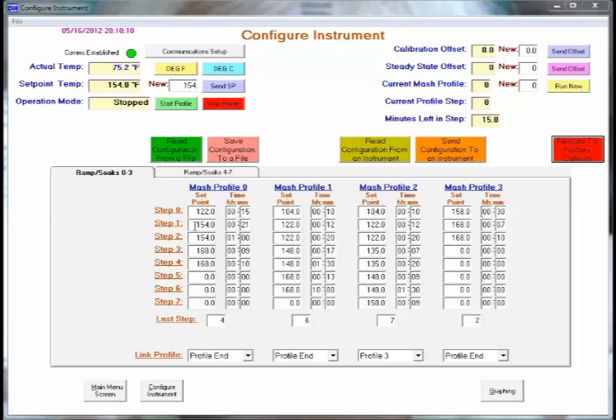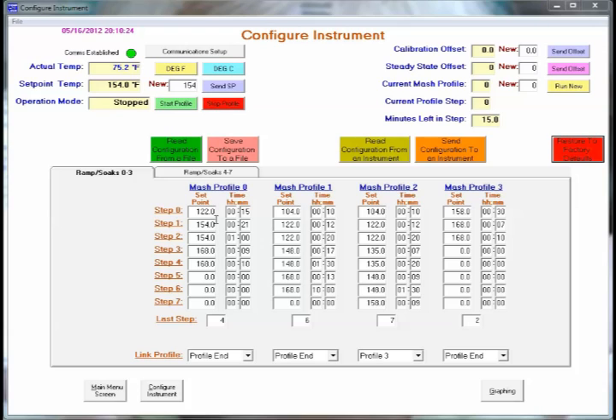After that we're going to ramp and we're going to ramp from up to 154 and we're going to ramp at a rate of one and a half degrees per minute. So to calculate the time we take 154 minus 122 and divide by 1.5. That would be 21 minutes. So it will take us 21 minutes to ramp from 122 to 154 degrees.